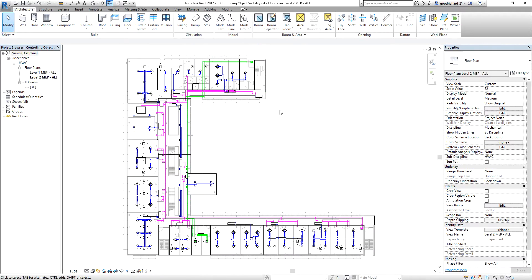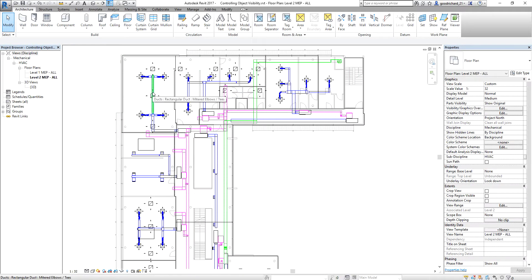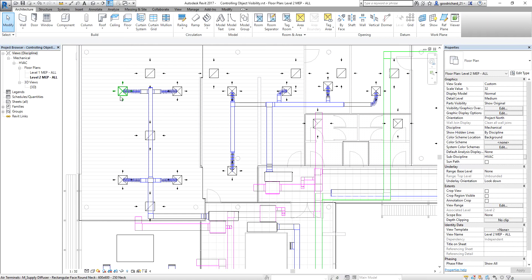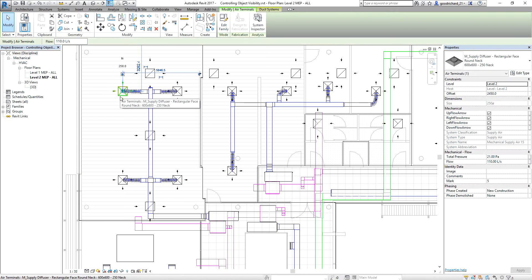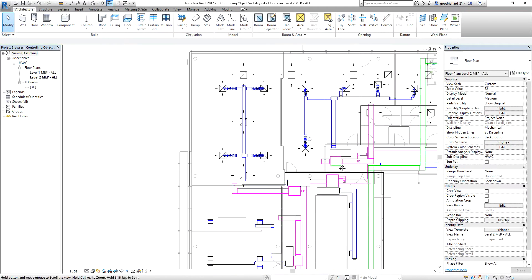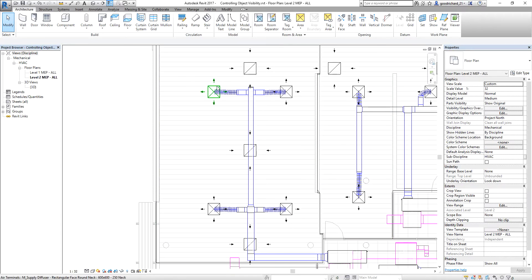By doing that, you will understand more how the system works on your project. The color blue is your supply, magenta is your return, and color green is the exhaust. In case you want to include the air terminal — if I click this air terminal, as you can see it's also supply air, but why doesn't it change to color blue? The reason is that you didn't include air terminals in the categories of the supply system filter.